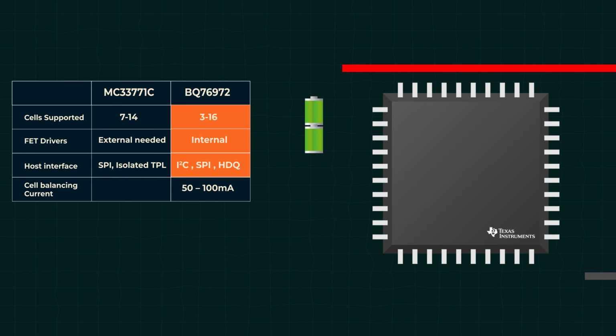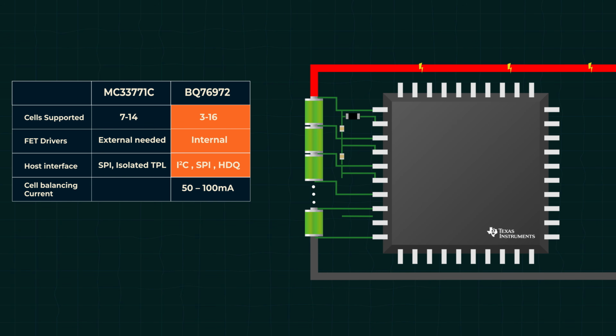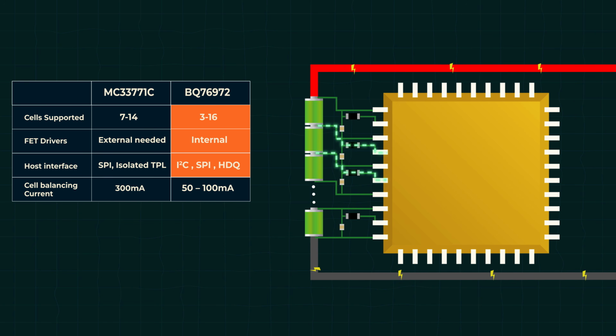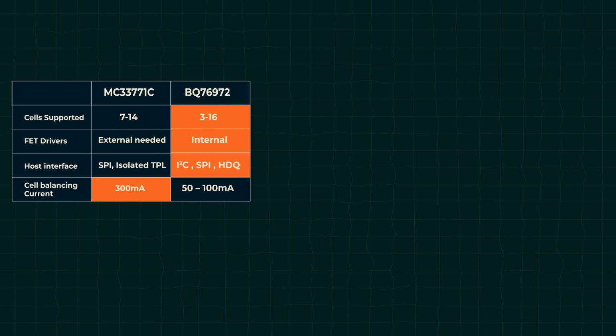Inside the BQ76972, each cell channel includes an internal bypass FET with about 28 ohms of resistance, handling 50 to 100 milliamperes of balancing current per cell. The other AFE can drive much higher balancing current, but for a smaller pack, this would be sufficient.